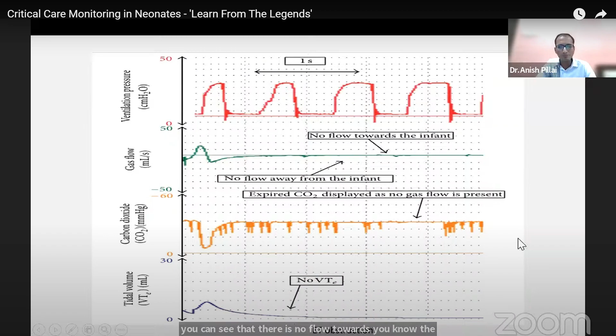Here also there is an event that happened. You can see the first half of this on the left side. You can see the graph, what is happening. The pressure seems okay. The flow is okay. And look at the volume, what has happened to the volume. So here the volumes are okay. And suddenly there is no flow in this negative part away from the infant. And the volumes are going up, up, up. Like there is no end to the volumes. They are not returning to baseline.